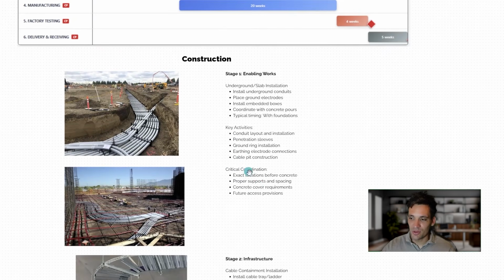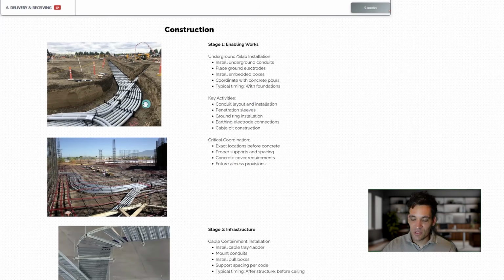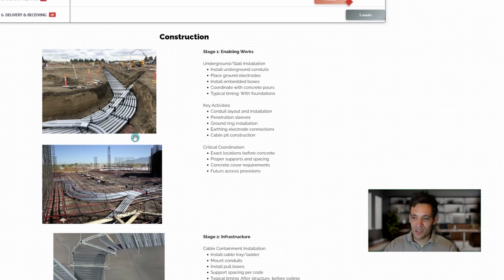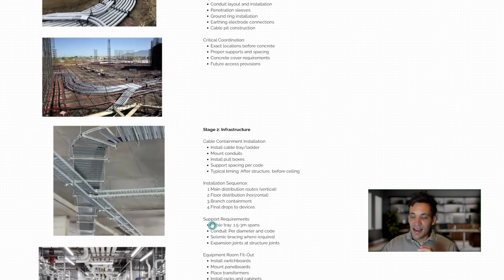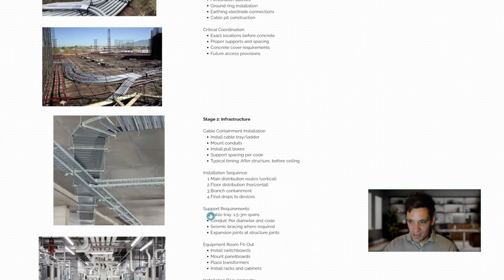So starting with the initial construction, the first stage of any electrical project is the underground installation. This is where you run your pits and pipes underground, you drill the foundations for your light poles, you run conduits through the slab. This is heavily coordinated with the civil and structural works, and it's essential that electrical people are managing this, because in my experience, when you have civil people doing this work, you always end up with missed conduits, blocked conduits, things not connected properly, conduits missing from the drawings. To me, this isn't a civil construction activity. Installing these conduits, penetrations, and earth grids is electrical construction. It needs to be managed by electrical people. The next stage happens after you've had the initial civil works, the slabs, the structures.